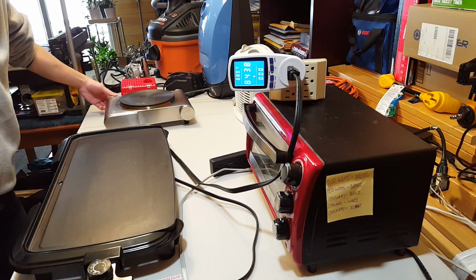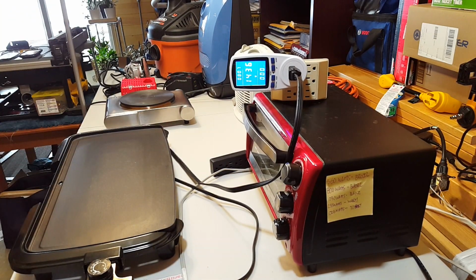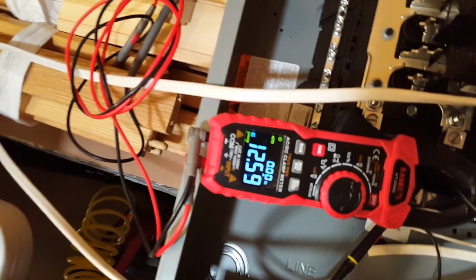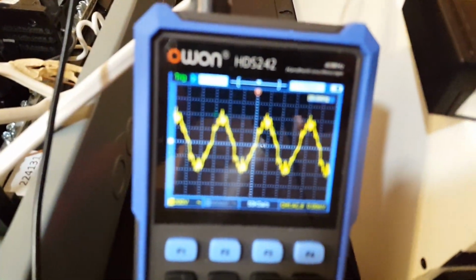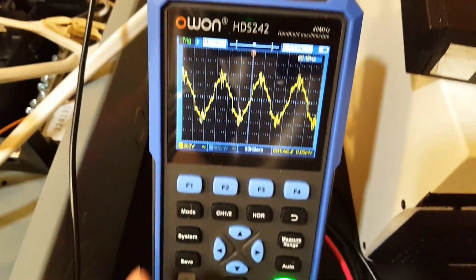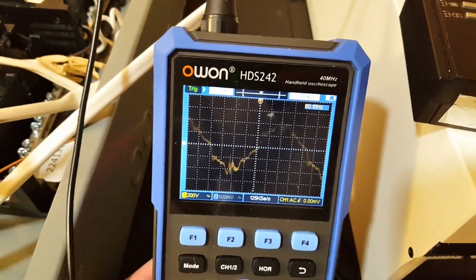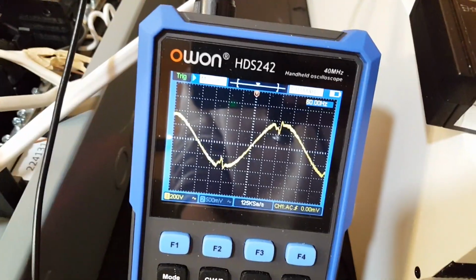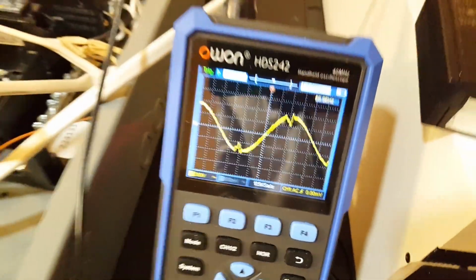Testing hot plate. It's doing 1436 watts. The amps, it is 12.6 amps. Bypass mode. This is the direct power sine wave. So the waveform is not as smooth in AC bypass mode, of course. Let's go to battery mode. There's the inverter waveform, almost perfect waveform.